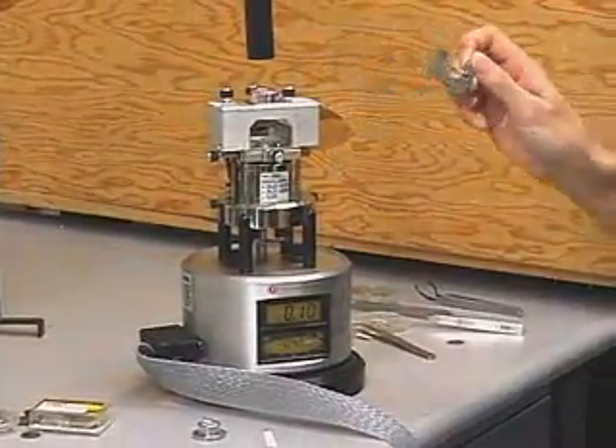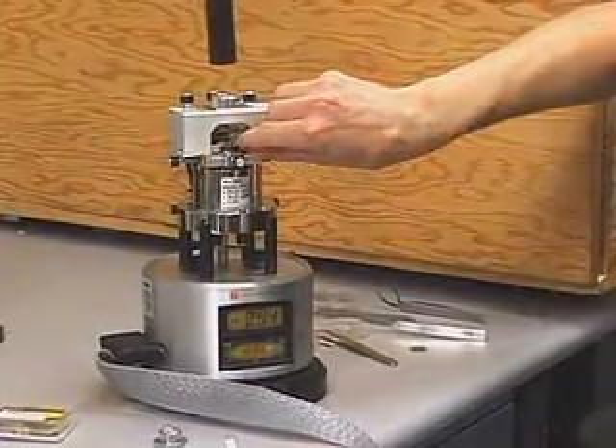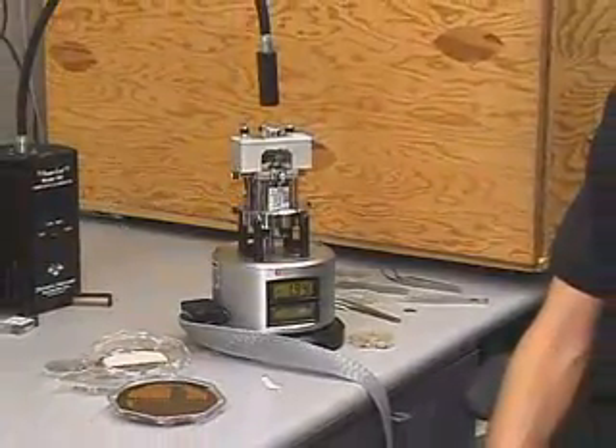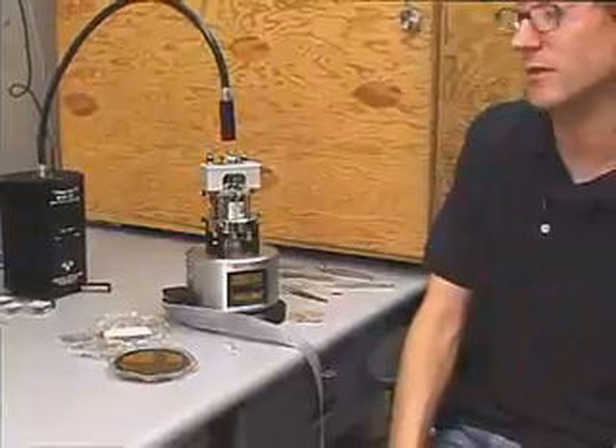It's actually mounted into this little clamp, and we put that into the microscope. Once the tip is in place, the laser is aligned so that it reflects off the very end of the cantilever. That laser spot that reflects off is detected by a photosensitive detector that can track the movement of the laser spot up and down as the cantilever scans over the sample surface.